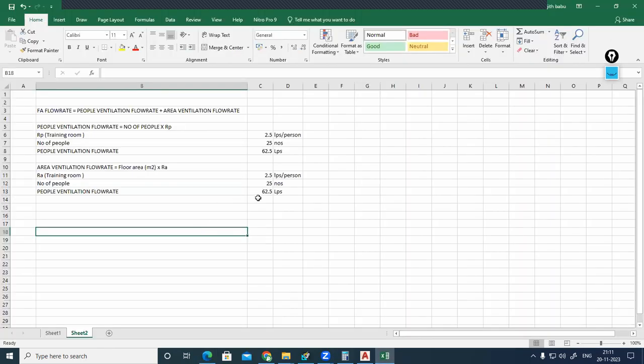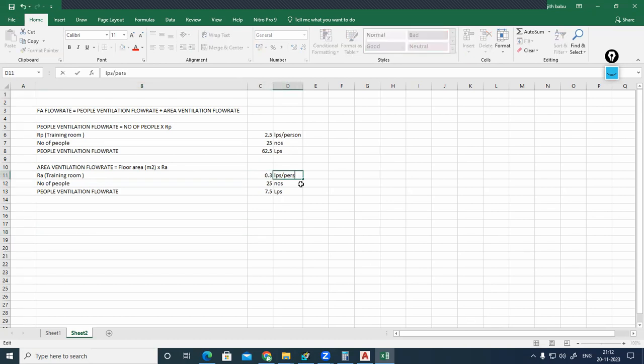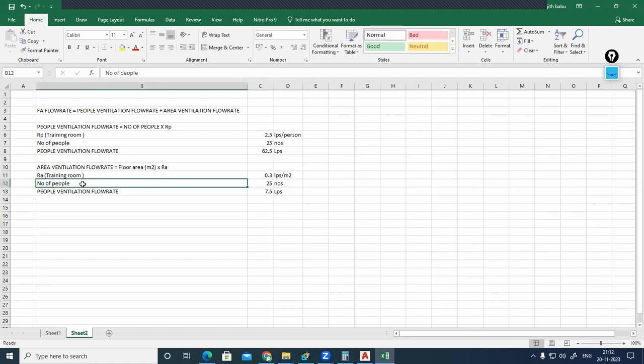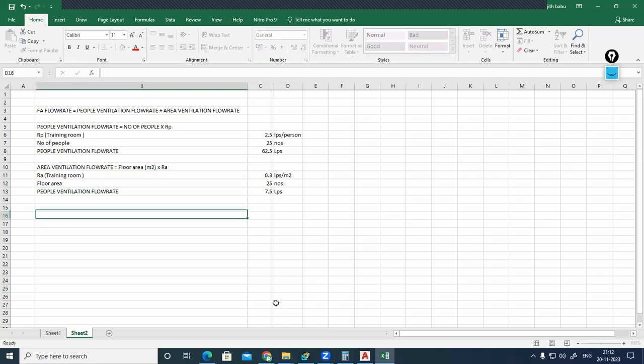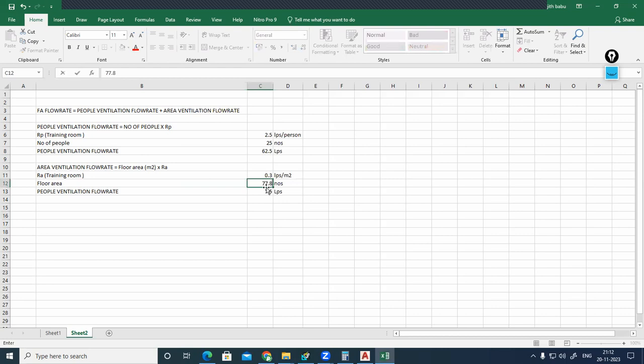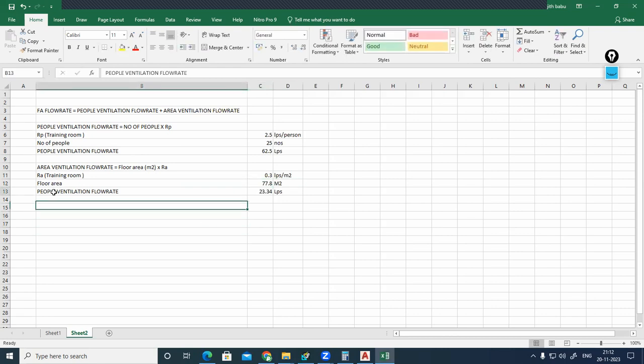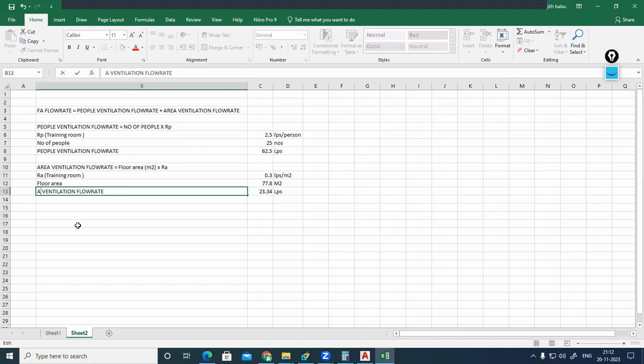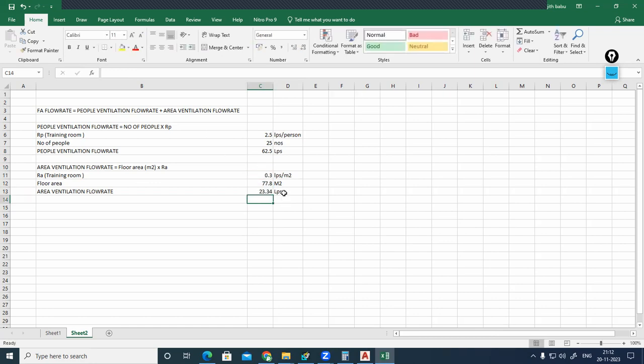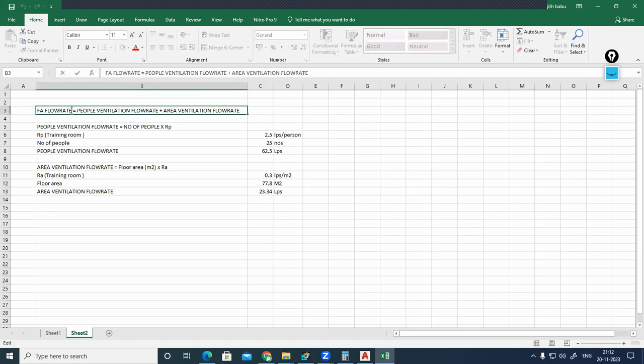Okay. That is people ventilation flow rate, area ventilation flow rate. Floor area that we are designing, you should find RA. RA of training room, we can consider 0.3 liter per second per meter square. The next one, we need floor area. Floor area, we already know, right? Here you can see for training room one, we have already taken 77.8 meter square. Floor area will be 77.8 meter square. Now, the area ventilation flow rate will be floor area in meter square multiplied by RA value, per meter square, liter per second per meter square, that is called RA. Liter per second per person, that is called RP. So how much we need? 23.34 liter per second.